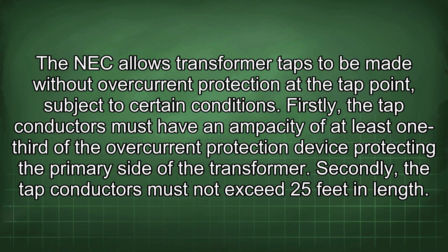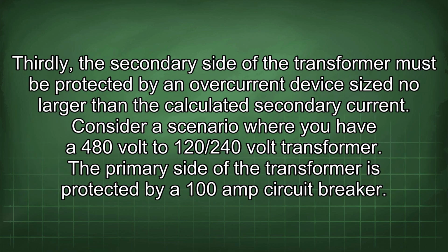Firstly, the tap conductors must have an ampacity of at least 1/3 of the overcurrent protection device protecting the primary side of the transformer. Secondly, the tap conductors must not exceed 25 feet in length. Thirdly, the secondary side of the transformer must be protected by an overcurrent device size no larger than the calculated secondary current.